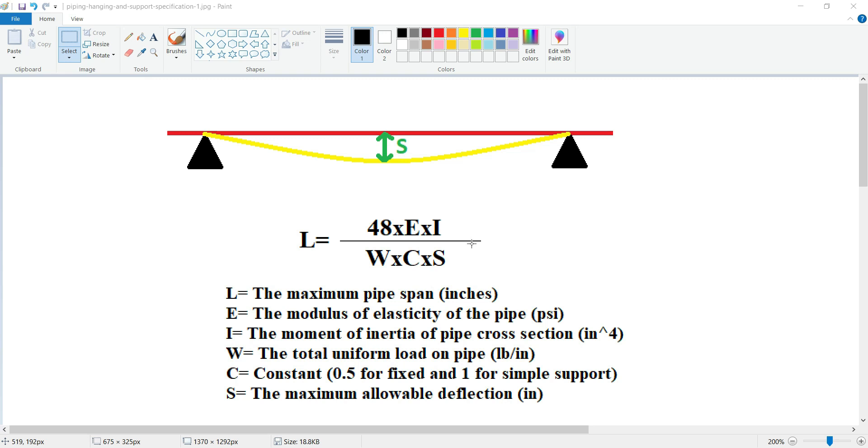Before continuing, just consider that supporting is a key factor in piping engineering because by supporting you have to optimize the flexibility and weight control of your system. If you use too many supports on your system, the flexibility is reduced and you don't give your piping network the required movements that it should have. By not using the required number of supports, the stresses in pipes is increased because the load of the items on your piping system is induced in your pipes, and these induced stresses can exceed the allowable load on your piping system and might lead to failure.